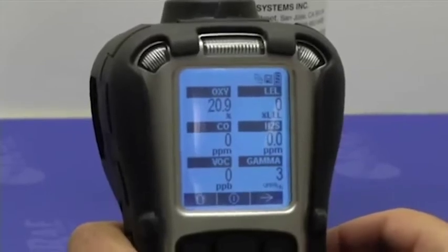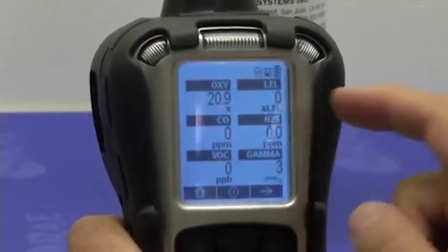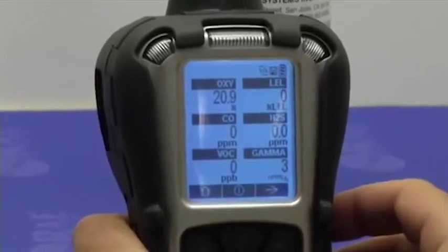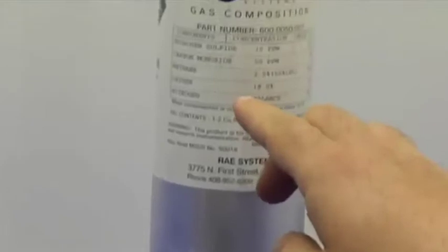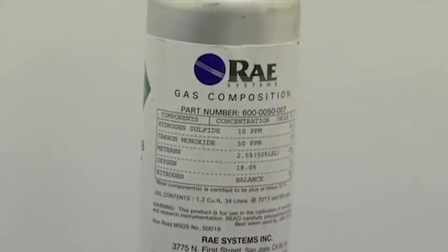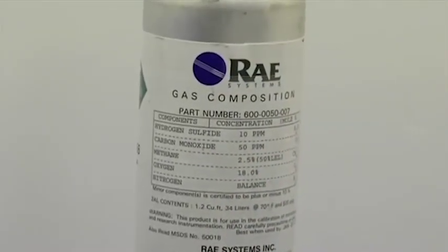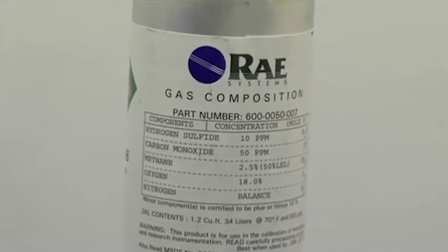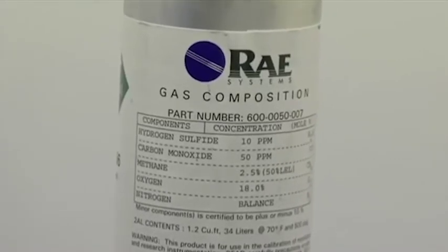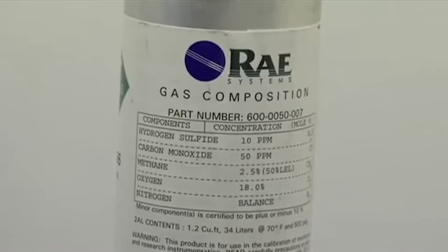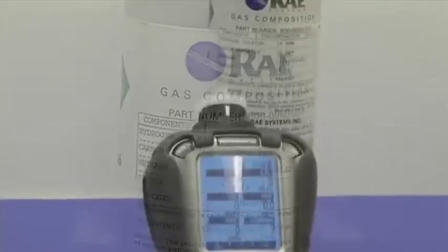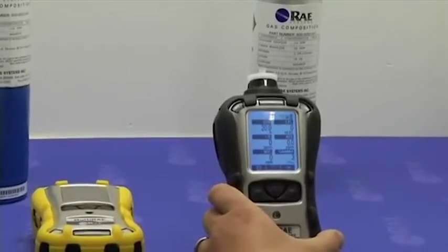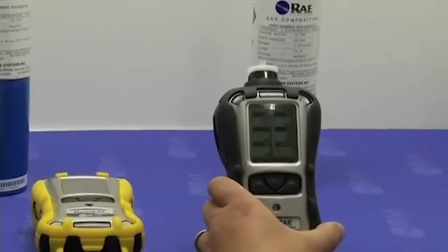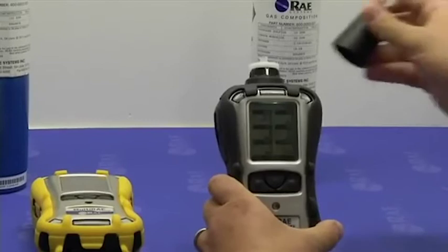First step, I'm going to bump test the 4 sensors, oxygen, CO, H2S, and LEL, using a 4 gas mix that contains 10 ppm hydrogen sulfide, 50 ppm CO, 50% LEL, and 18% oxygen. Any MultiRAE should be bump tested with a calibration adapter, regardless of whether it's a diffusion model or a pumped model.